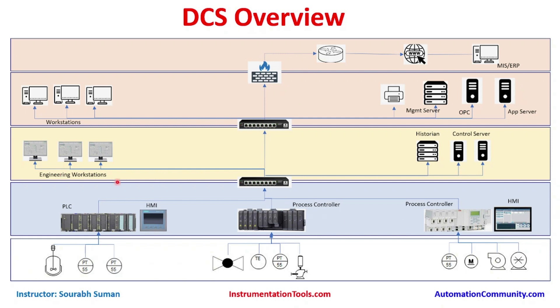We also have engineering workstations and operator workstations in the DCS. From the engineering workstation, we can program the controllers — for example, in a turbine control in a power plant, we can download new logic, modify business logic being executed, perform graphics tasks, set the archive, and everything else.